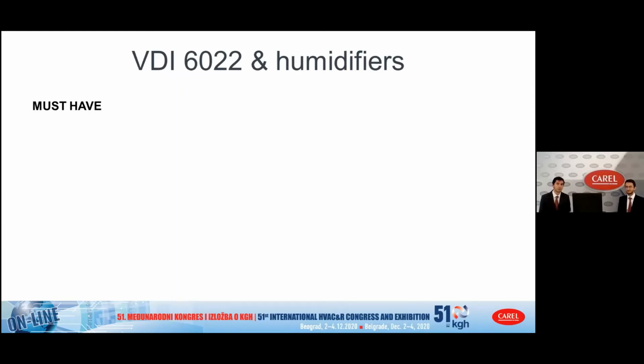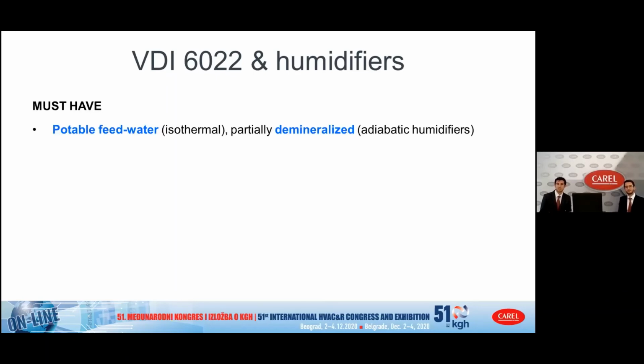So VDI 6022 gives some real technical suggestions. A humidifier, in this case, must have good feed water as a starting point. If we are using a steam humidifier, the water must be clean, drinkable, potable. If we are using adiabatic humidifiers, the tendency is to suggest demineralized water, at least partially—we will see why.